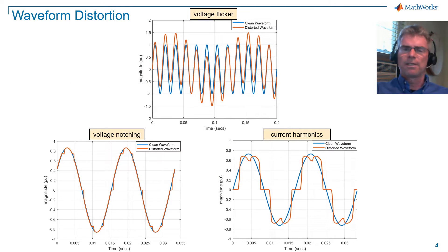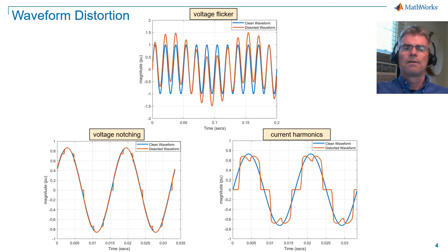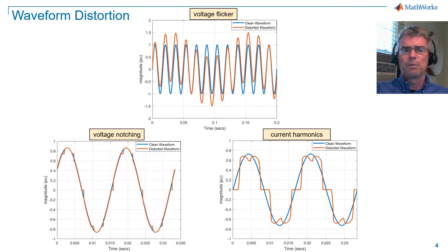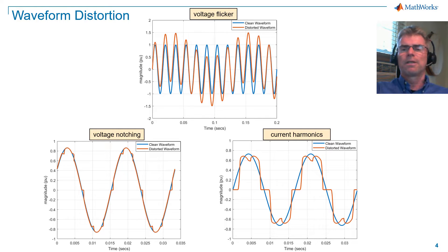When a waveform is no longer a perfect sinusoid, we say it is distorted. I'm showing three types of waveform distortion here: voltage flicker, voltage notching, and also current harmonics. Flicker is so called because the human eye can detect it when flicker causes lights to flicker. The frequency of flicker detectable by the human eye is around 8 to 10 hertz. Flicker is caused by rapidly changing loads on the broader electrical system. At the top, you can see one representation of flicker, where I've added an 8 hertz distortion to the main 60 hertz supply. Notching is where voltage is disrupted for a short period of time within a single period, and is typically caused by power electronic switching. The notching I'm showing here is caused by a three-phase diode rectifier. I'm only showing phase A line voltage for clarity. The third example is phase A line current for a three-phase diode rectifier.